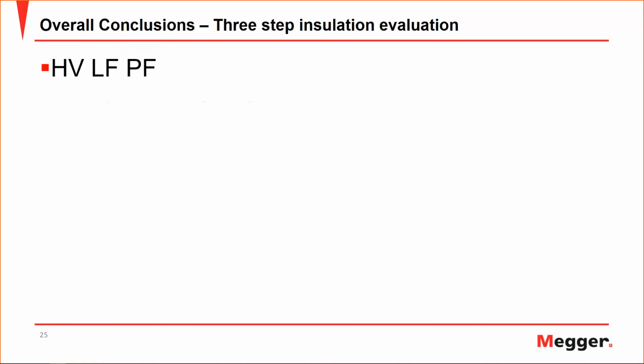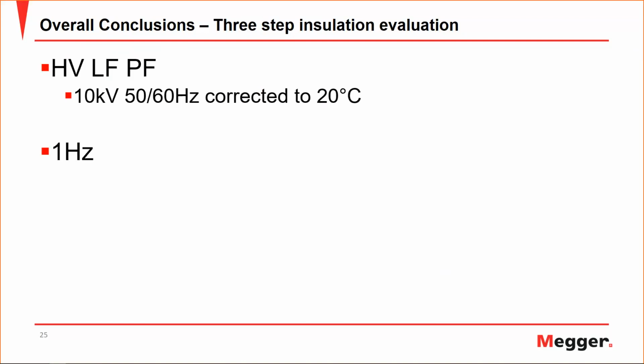The first is going to be high voltage line frequency power factor. Of course, this is your 10 kV, your 50-60 hertz corrected to 20 degrees C, and it's required by standards. So we know that you're not going to stop doing that today. And that is why we want to introduce the 1 hertz, because again, it's using that same connection that you're already required to use today. And then we're just going to run one additional test that takes less than 1 minute at 250 volts, and then correct that 1 hertz value to 20 degrees C.